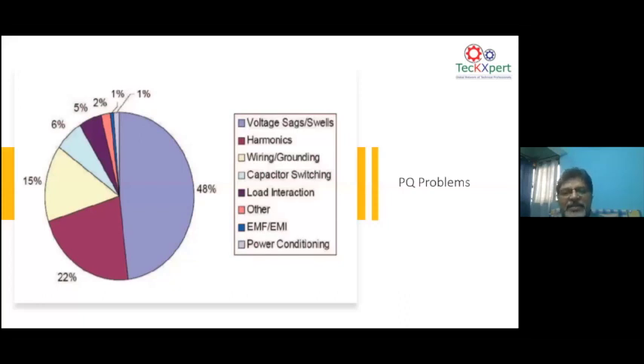There are IEC standards which tell how much a power electronic device is supposed to pollute the grid or the power system, and how immune these electronic devices should be. That means EMI and EMF are very important in power quality, because many power electronic devices, if you just let them go loose, can produce so many harmonics or other electromagnetic emissions. And those emissions, sometimes the connected equipment in the grid may not be able to withstand. The immunity of those equipment may not be proper. That means EMI and EMF become another power quality problem.